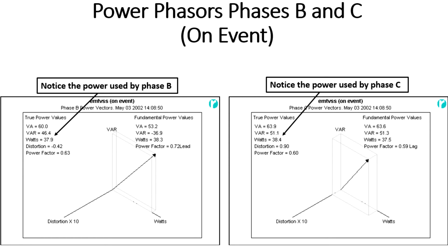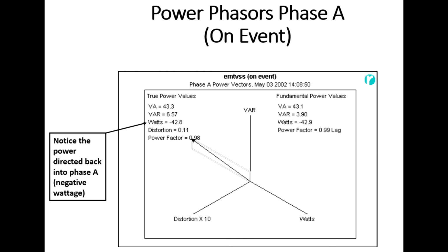We've talked about volts and amps. Well, how many watts of power does this take? We'll notice here on phases B and C, it took about 38 watts of power. So this is an extremely energy efficient solution to power problems. We can see the power phasors for phase A. The wattage is shown as negative 43 watts. So you can see this is actually the power being directed back into phase A. That's why it has the negative in front of it.